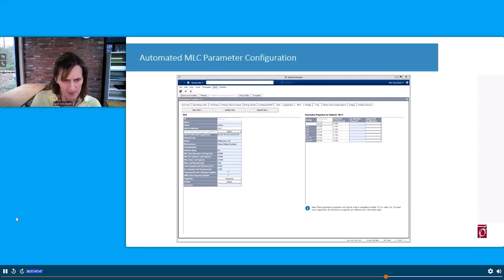In the Eclipse 18 version, the MLC parameters that you use to put in RT administration will no longer be used. If it's confusing to you that they are there, you can delete them, right? You will now have to input them into beam configuration, right? And in order to be able to do that, you will need to have the measurements, the results of the measurements ready.